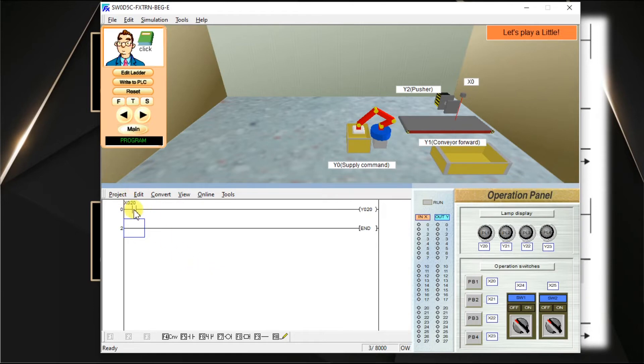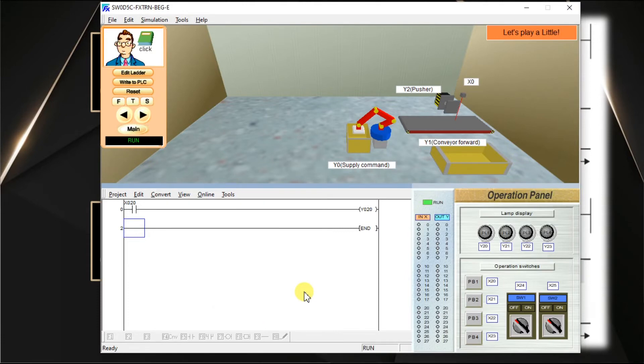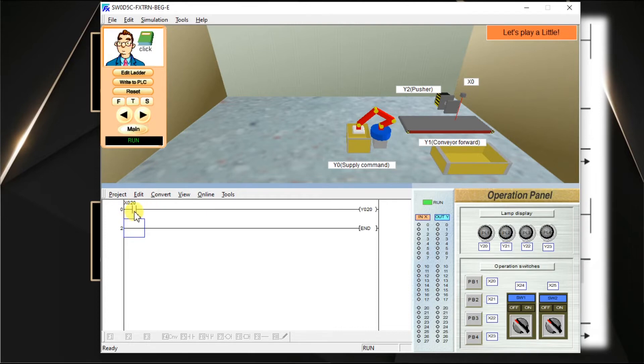Now we have to download this logic into the PLC. Click the Write to PLC button. The program will be downloaded into the PLC — click OK. The program is successfully downloaded. We can see the status here. The PLC mode changes back to run mode. Now in run mode we can do our simulation. This is a normally open contact, so the output is already in the off state. If I activate the input, the output will also be activated.